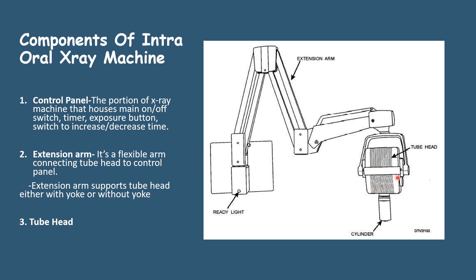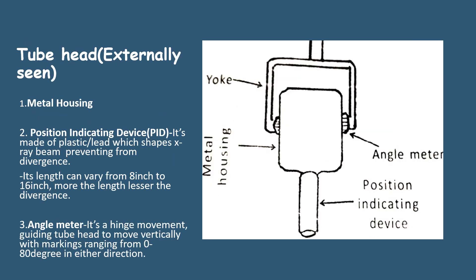This is the tube head. The tube head consists of two parts: ones which are externally seen and others which are internally present. The externally seen parts consist of the metal housing, the position indicating device or PID, and the angle meter.